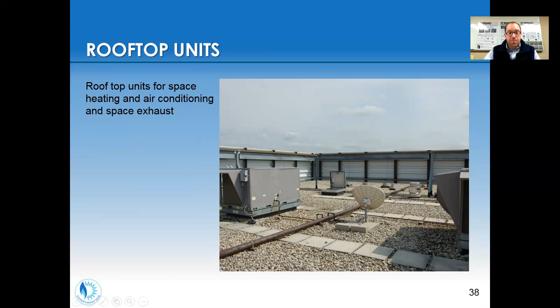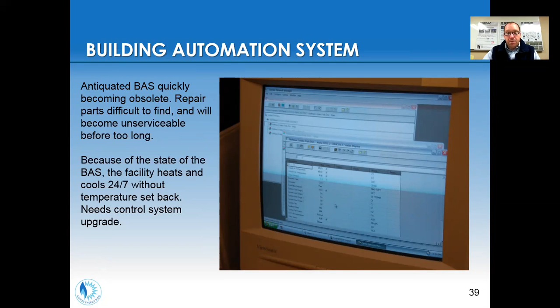This example was an antiquated building automation system on a computer, and computers can quickly become obsolete, so keeping on top of that is important. Because of this, the facility was almost abandoned and not being maintained. The programming had it heating and cooling 24/7 without temperature setback or any changes in ventilation. So it needs a control system upgrade, which will help a lot in this large building. The bulk of the energy savings in this case came from turning the fans off and turning the heating down at night.